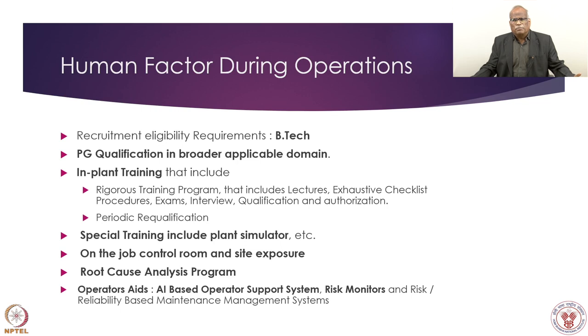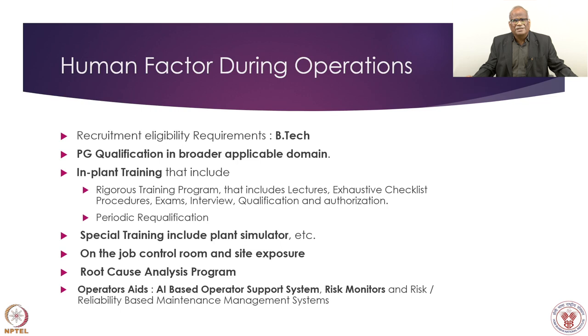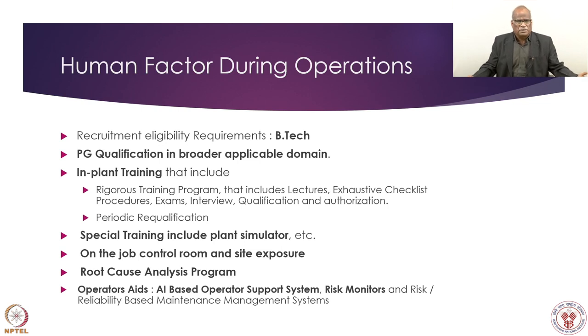Root cause analysis addresses human factors, and once the root cause is understood, modifications can be made. Intelligent operator support systems are being designed for control purposes. Risk monitors are being designed so that if a component is taken out of service, the operator knows the impact on risk and can perform the job without affecting available redundancy, diversity, and safety margins. Risk-based maintenance and reliability-based maintenance have become normal ways of life in safety-critical systems.